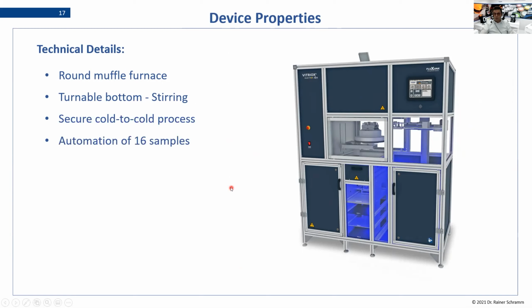We could automate it to 16 samples. That means even if you buy it only for 4 samples, you can later extend the machine to 8, 12, and 16 samples, just with a small software change and the additional holders you need. It's a modern network concept, so the user interface is Windows. So you are open to the Windows world. For example, if you would connect to LIMS or any kind of network connections you need, or barcode readers, or whatever you want to connect, this is all ready for the user interface.